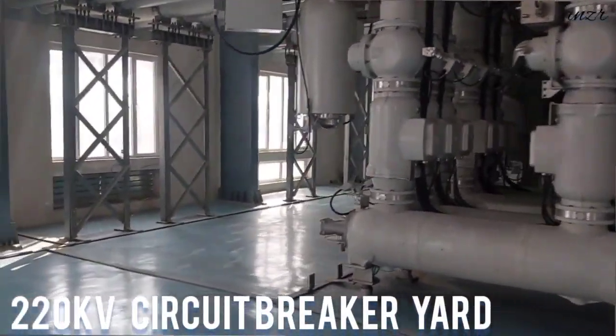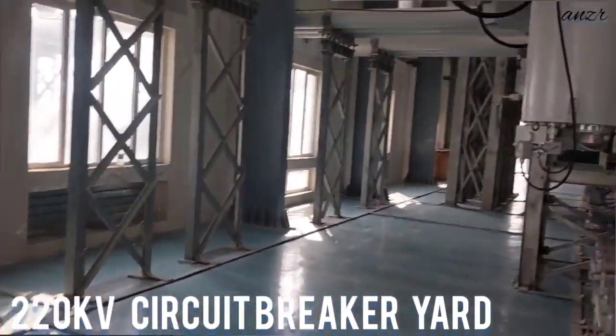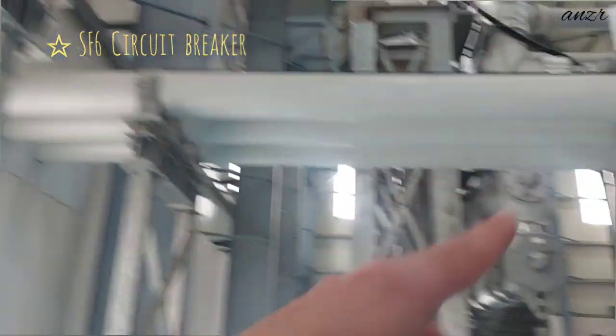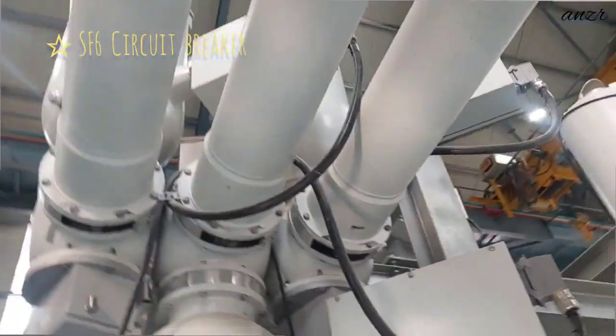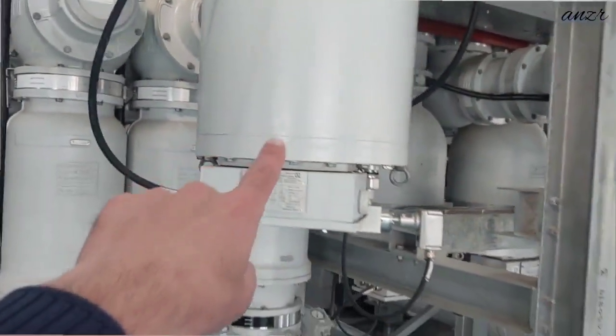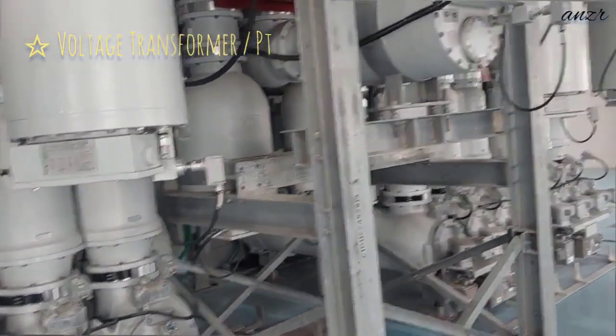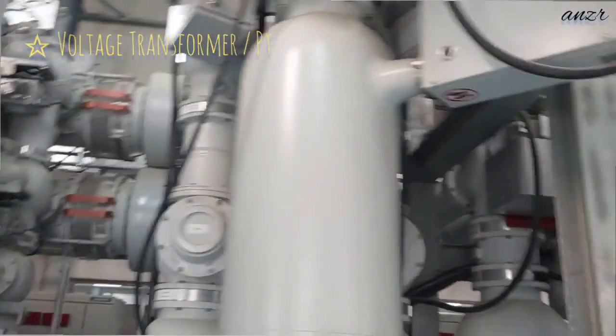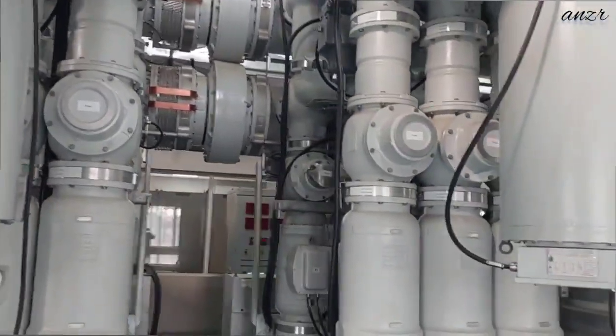This is the main part, the main crux of this GIS grid. As you had seen those buses, they are here. You can see this one is a voltage transformer, or potential transformer. It measures the incoming voltages and transfers the information to a relay, so that in case of excess voltage the system can be tripped. This is that side of the bus.